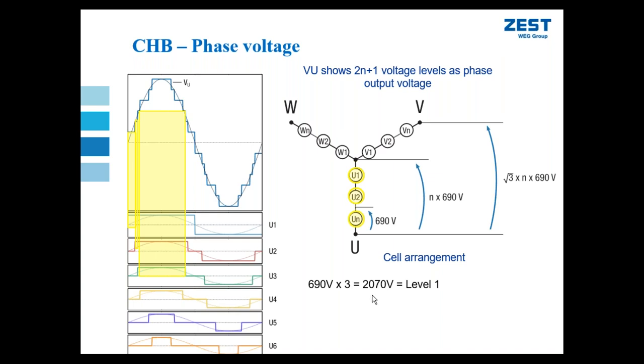So just to check the levels again. At this point, I am switching 3 690 volt power cells. That gives me a total of 2070 volts. That is my upper level, my highest level. I can then take my third power device, stop switching, switch only my two inside devices, and I reduce to 690 volt times 2, which is 1380 volts. That is my second level. And then my first level is 690 times 1 equals 690 volts. And then, of course, I can switch at 0 volts. I don't switch any of my devices, and my motor will see 0 volts at its terminals. And that is my fourth level.